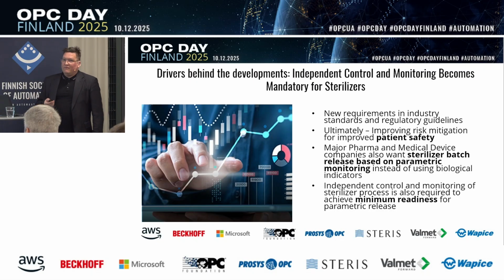This is why the sterilizer process validation standards and equipment requirement standards have recently been implemented with requirements for independent monitoring of the process controls—the critical variables specified by whatever sterilization method you're using. Typical things are time, temperature, pressure, and if you're looking at low temperature chemical sterilization methods, also gas concentration.